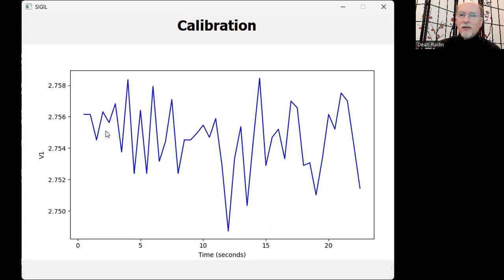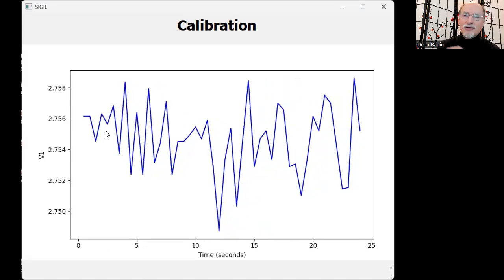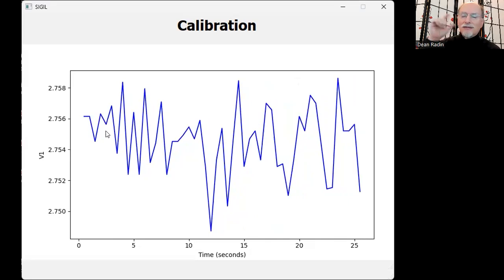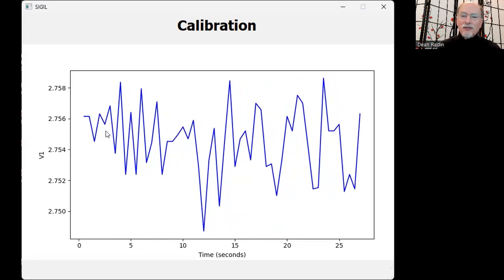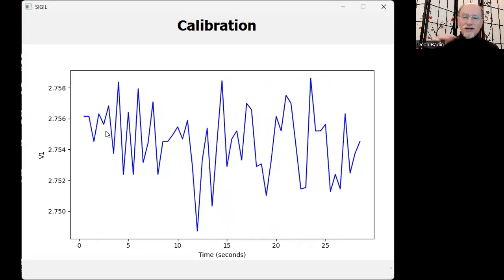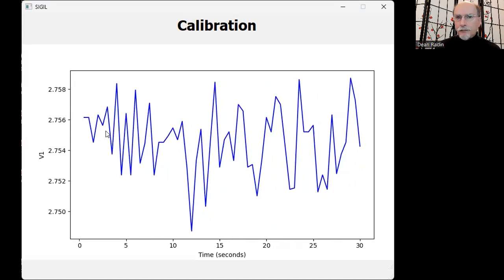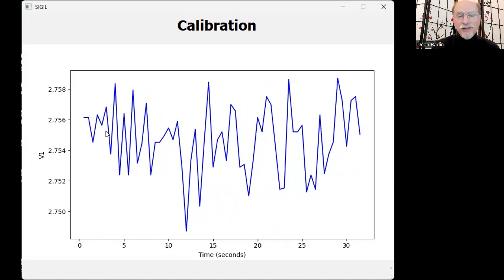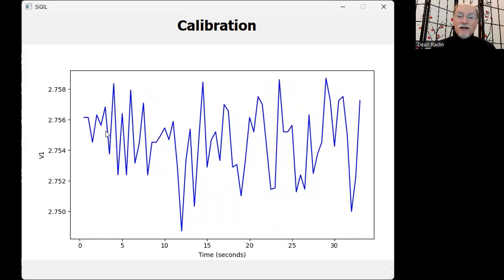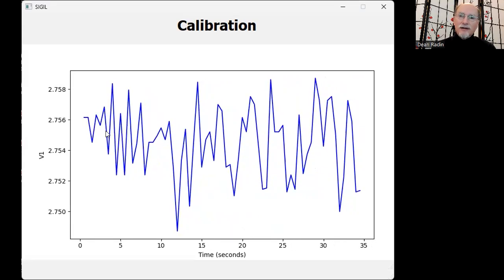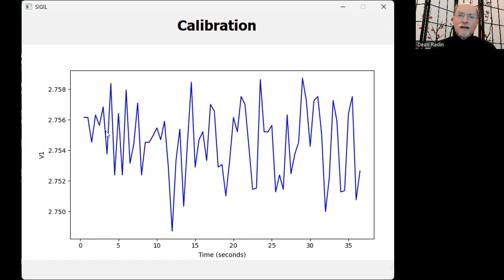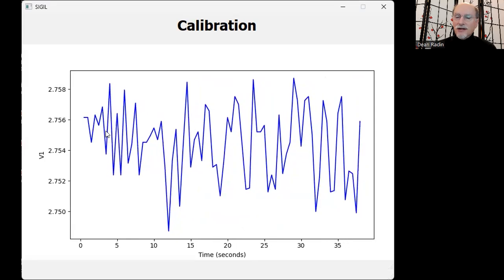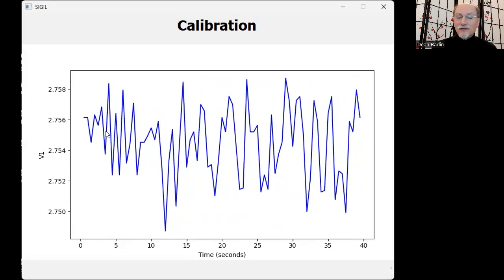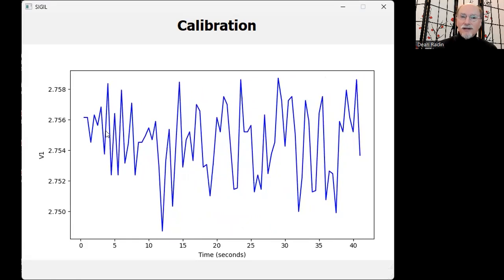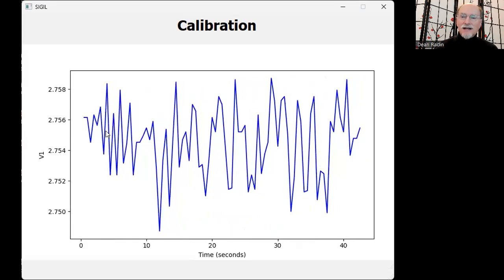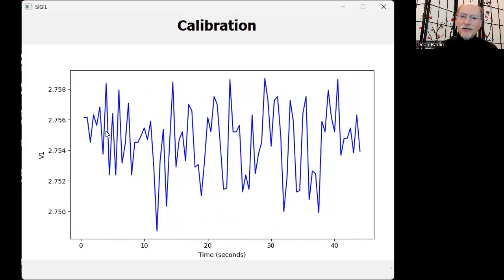Most of the time, it'll be pretty stable like this. You're looking at extremely high resolution, which is why it looks very noisy. If you were able to pull back a little bit, you'd see it's actually quite stable. And sometimes you'll see that there are oscillations. You might see the oscillations more clearly when this goes on for many minutes. And that's because the laser gets warm as it goes longer. And so the box takes about 10 minutes to settle down and get a stable signal.